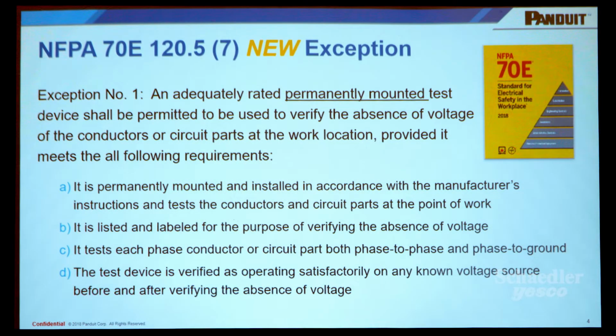UL recognized the AVT as an approved test device for de-energizing of electrical panels. In 2016, it was recognized. The NFPA 70E added it to the 2018 revision.